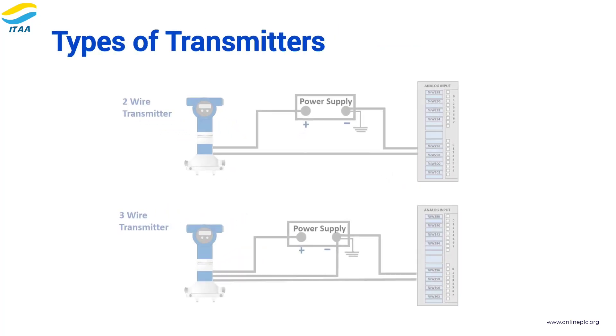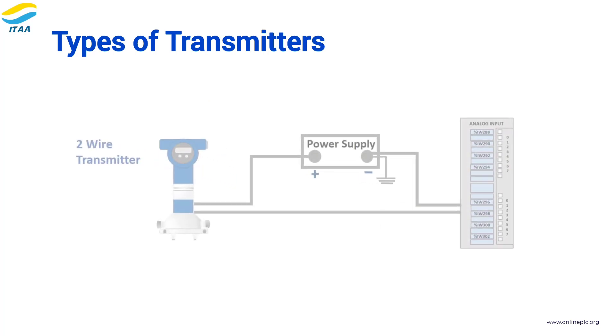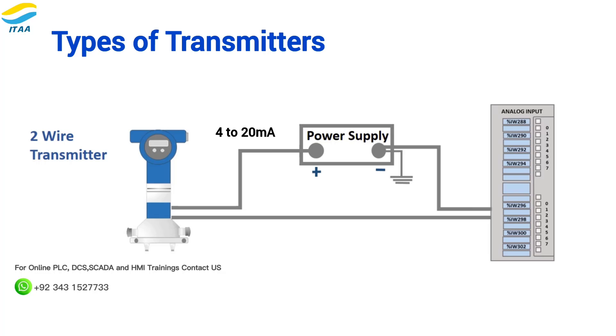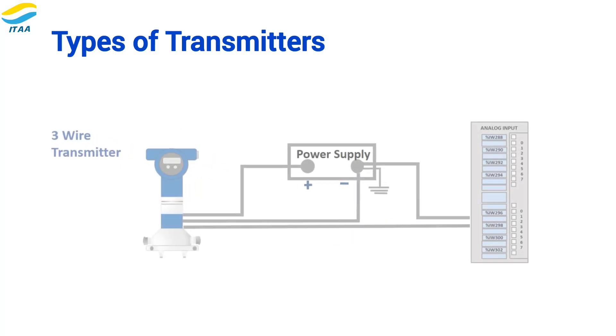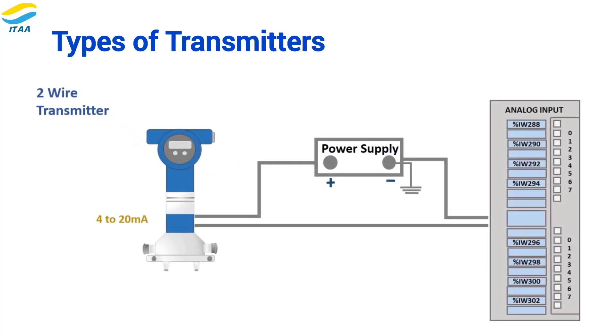Let's quickly talk about two types of transmitters you'll commonly see in industrial setups: two-wire and three-wire transmitters. Two-wire transmitters are widely used in automation — they have two wires that carry both power and the signal. In a 4 to 20 milliamp setup, the transmitter draws its power from the current loop, which makes installation simpler. Three-wire transmitters have a separate power wire, making them ideal where more stable power is required or when we need to separate signal and power lines to reduce noise interference. In this example, we're using a two-wire transmitter sending a 4 to 20 milliamp signal.